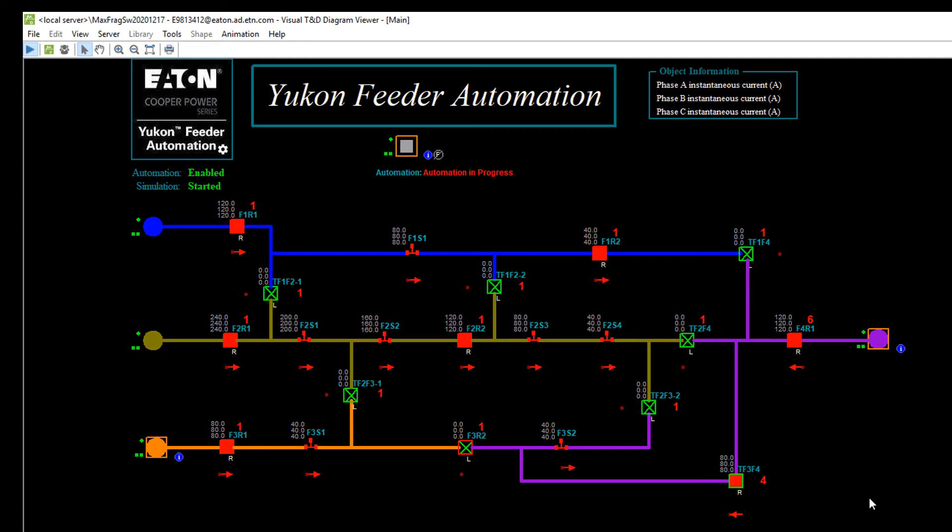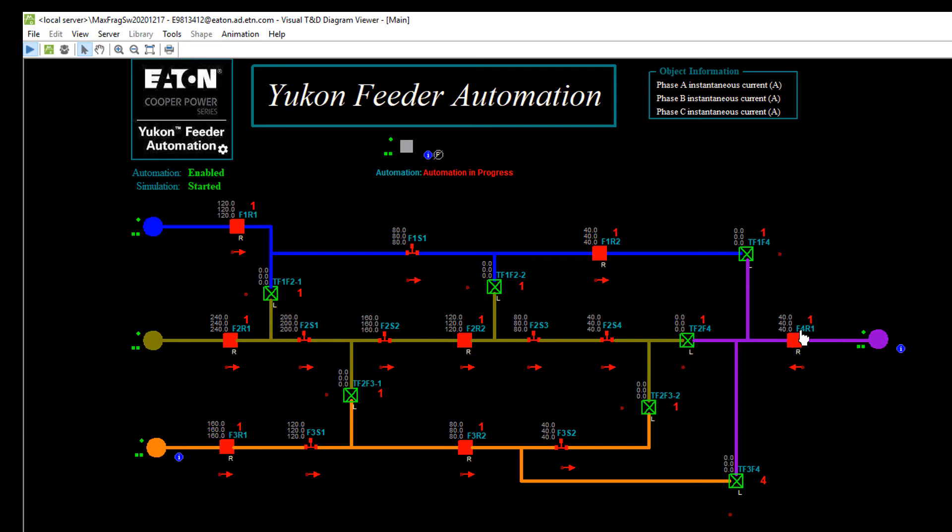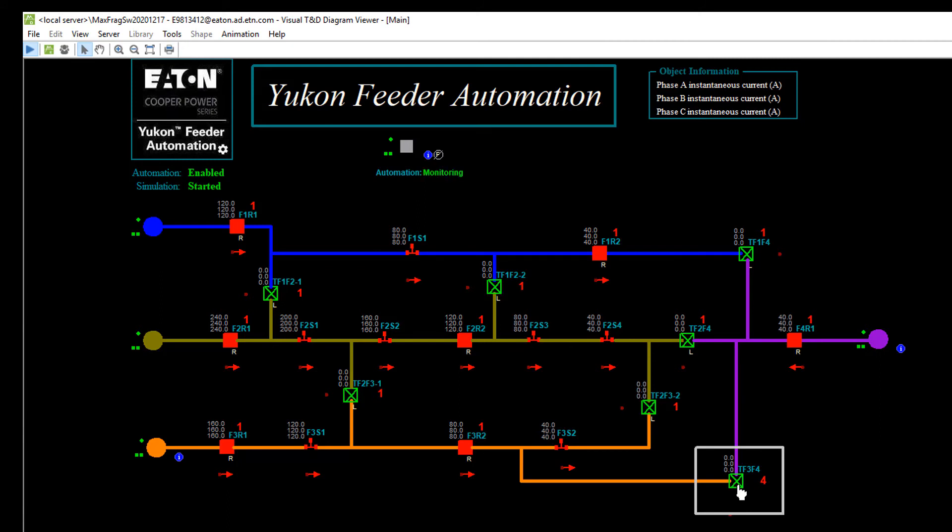Issue the return to normal command, close in that device, and open that one. We'll notice that this device switched its profile back to number one because it's in its normal topology. But this one stayed at four because now it's not fed by either feeder, so it just stayed in the profile it was. There was no new trigger to change back to any one particular profile, so we left it in profile four at that point.